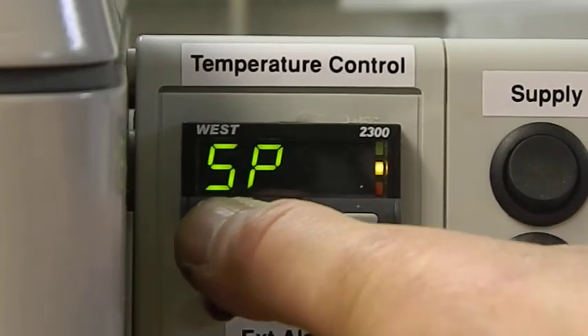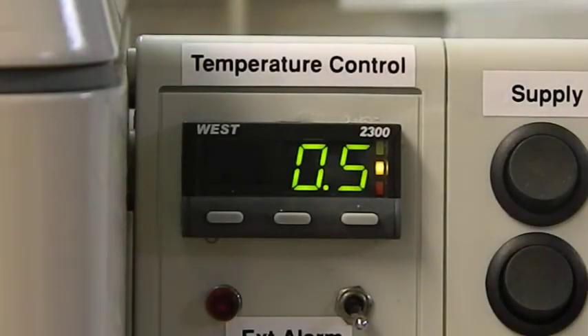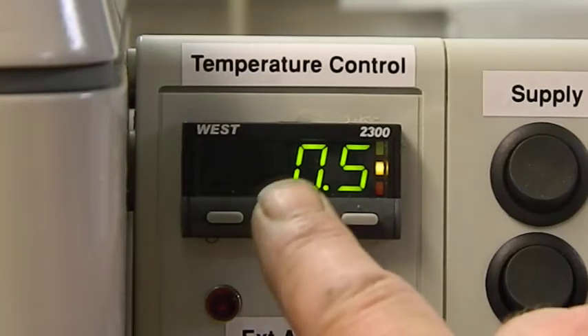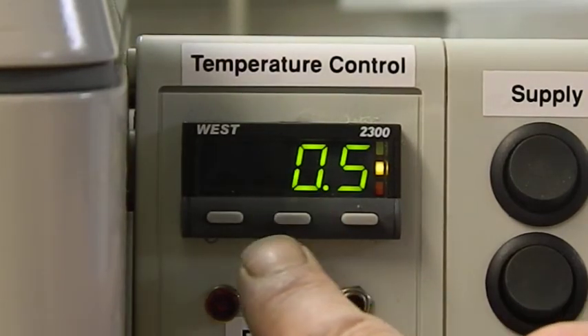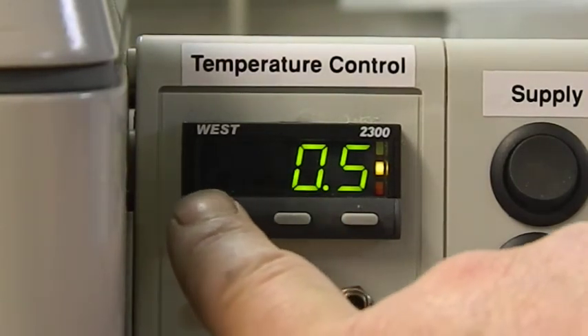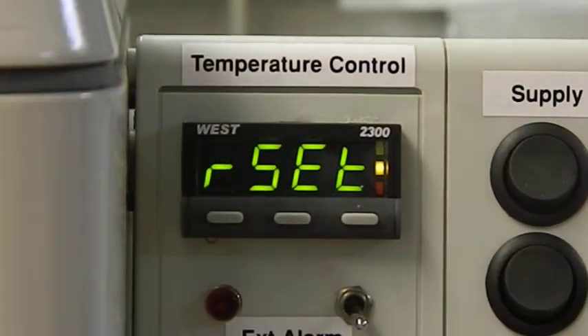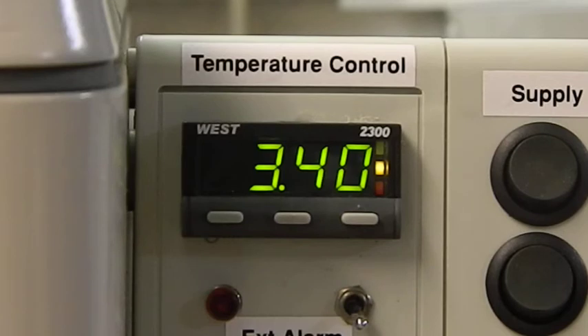Okay, so press the left one twice. PB, proportional band. This is the amount either side of the set point that the controller will allow to control within. 0.5 is the lowest setting. You can't lower it any more than that, so that's the lowest setting. That's where you need to be for that one. Reset, this is how quickly it recycles its measurement and correction program. 3.40.